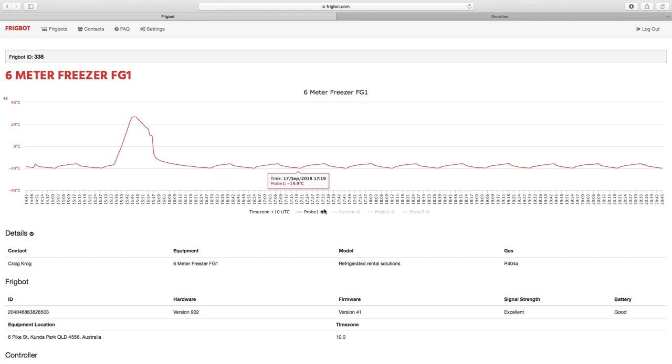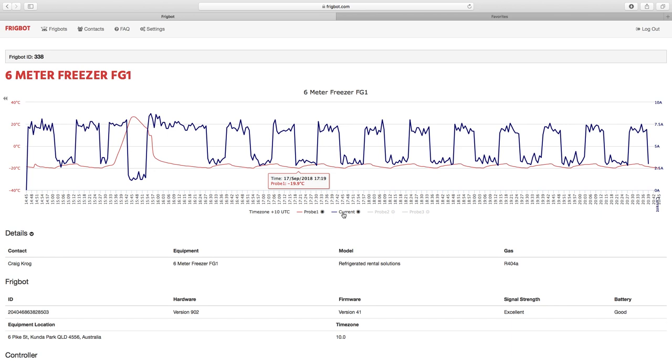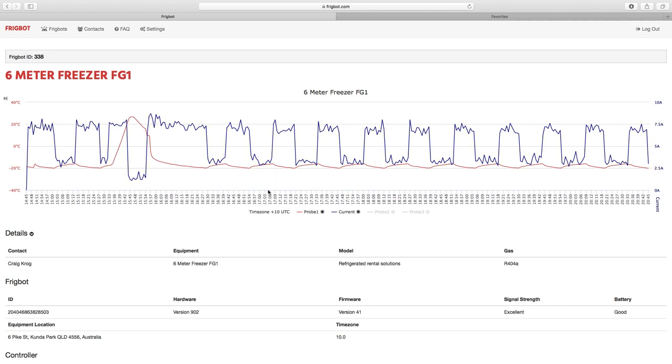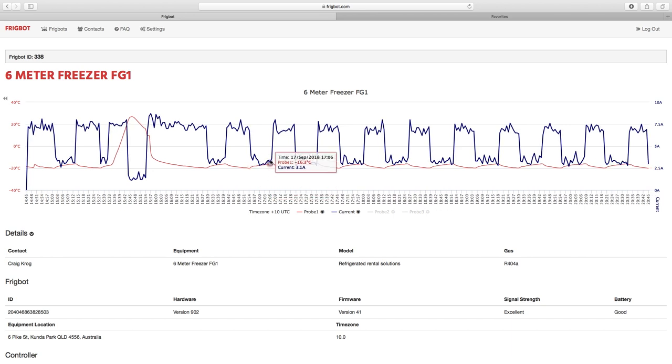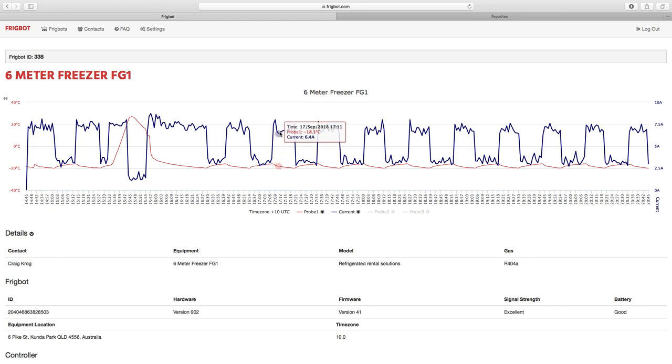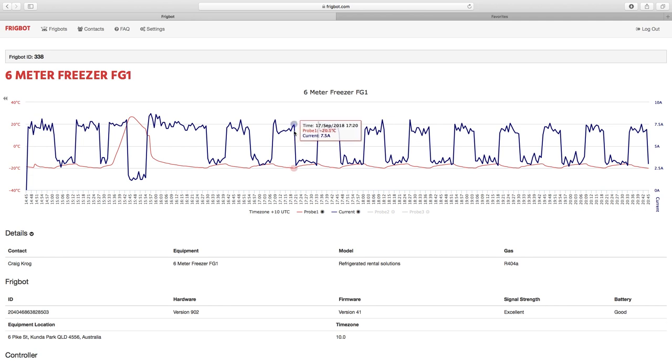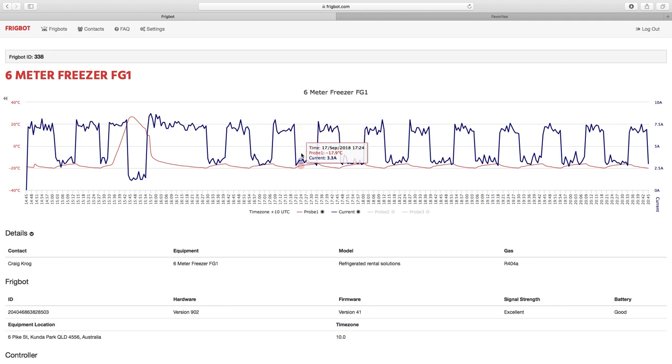So let's have a look at the current draw. Here we can see when the room is running it's drawing between 7 and 7.5 amps, and then once the room hits its desired set point we can see the current draw drops down to around the 2.8 to 3.2 amp mark.